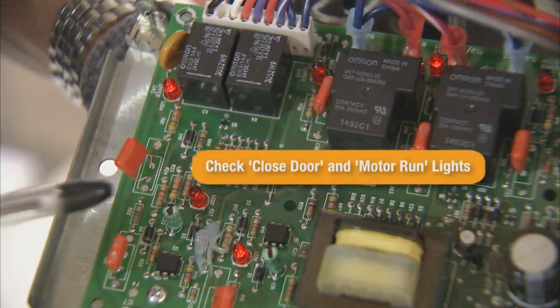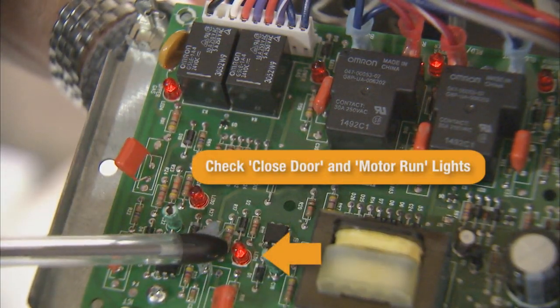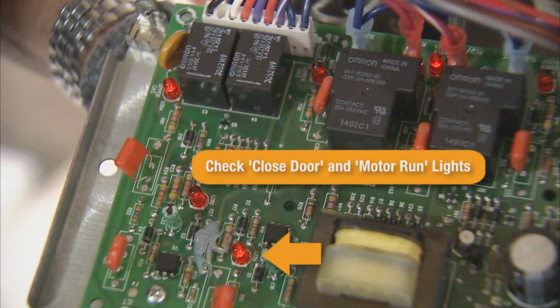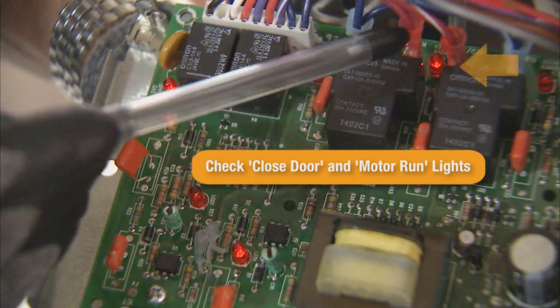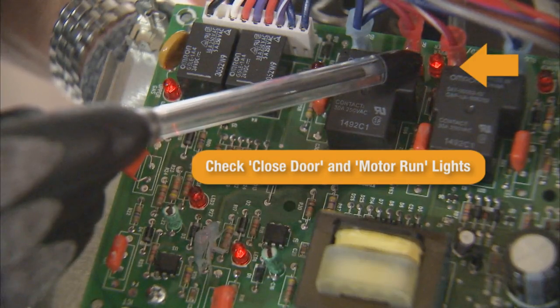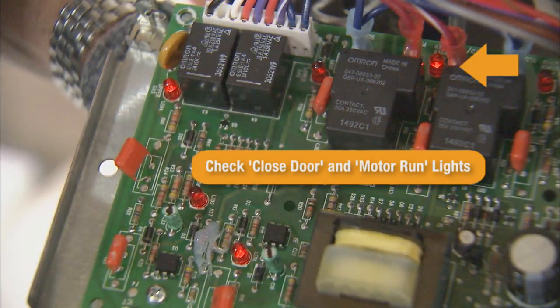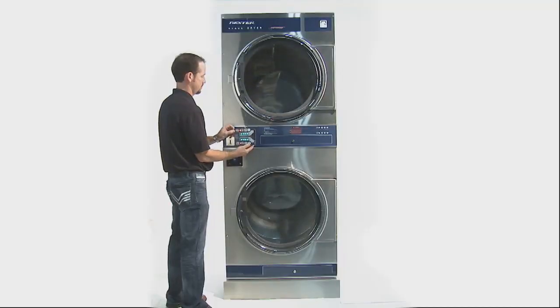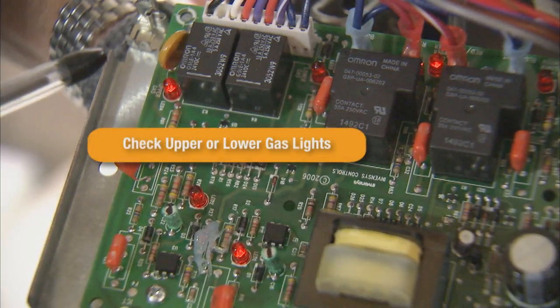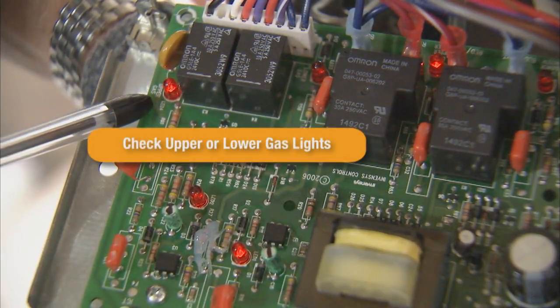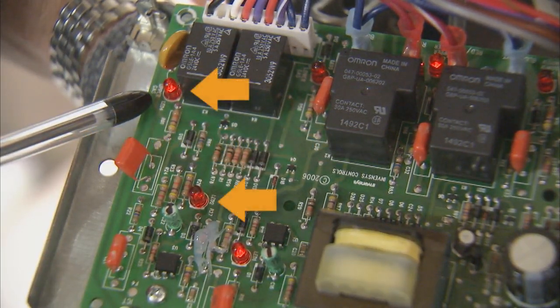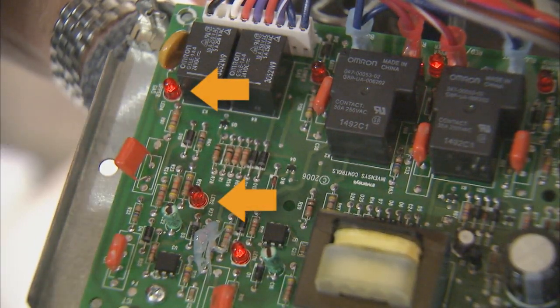If the drying tumbler is rotating, the door light for this drying tumbler is illuminated, indicating that the door switch is working. The motor light for this tumbler is also illuminated, indicating that the control is attempting to send voltage to the motor. The motor should now be tumbling the drying pocket. Next, check that the correct gas light is illuminated for the drying tumbler that is activated. This light indicates the control is attempting to heat the tumbler unit.